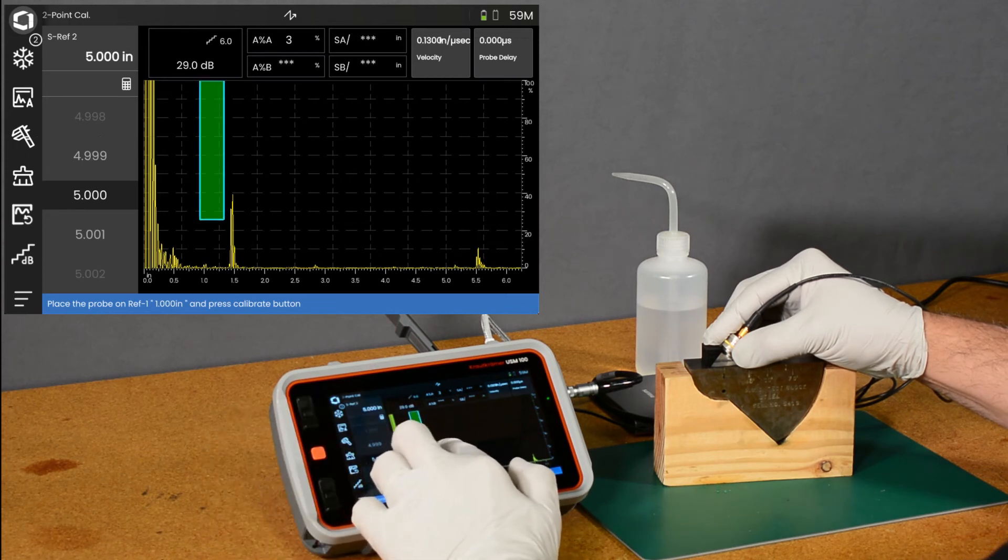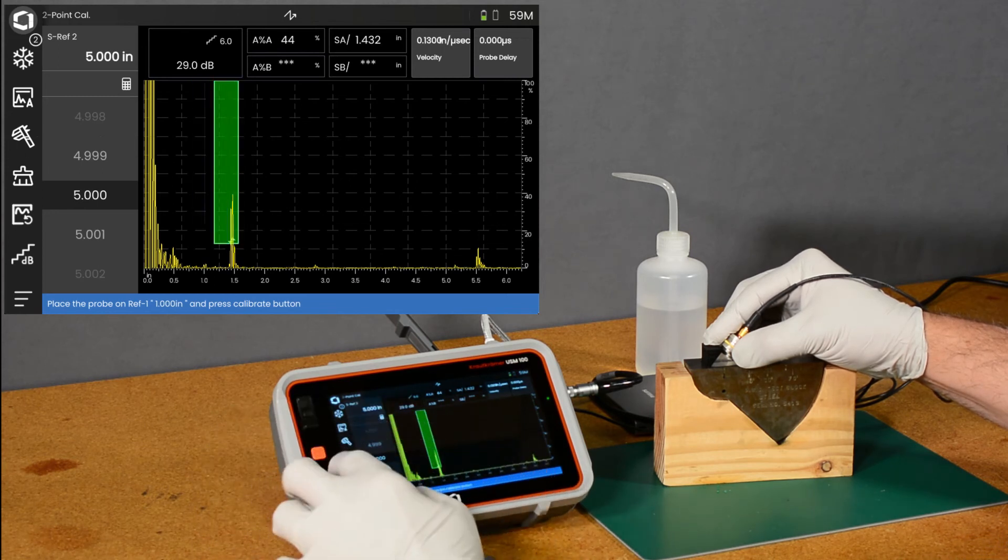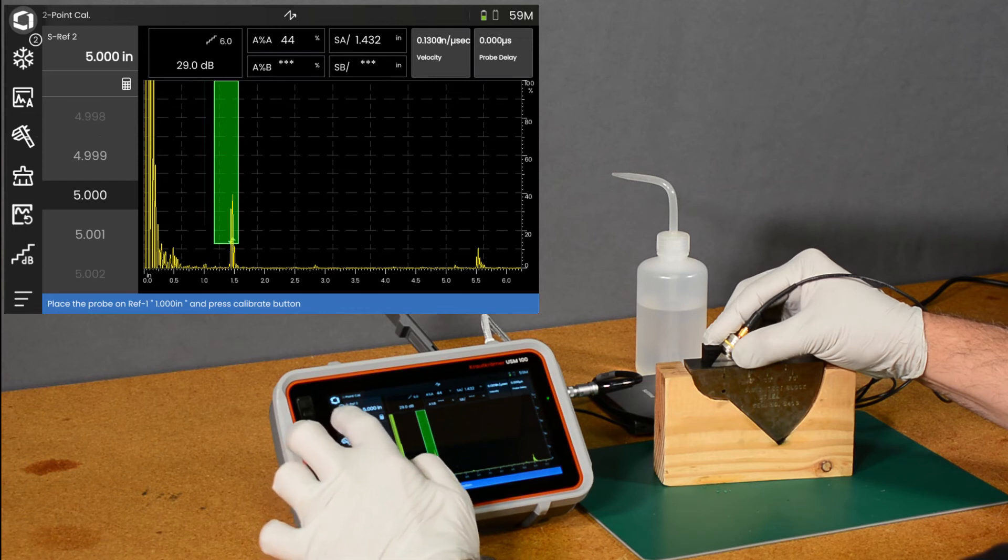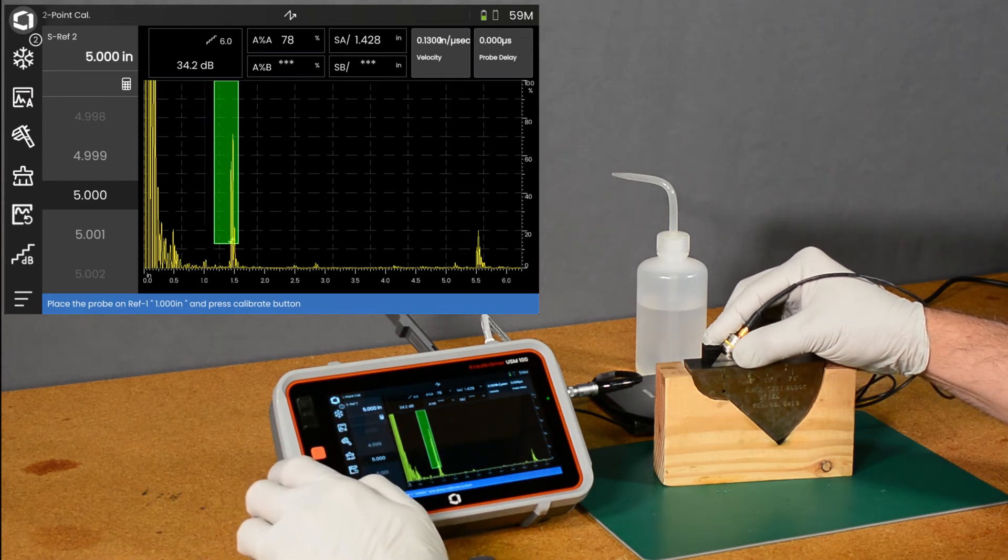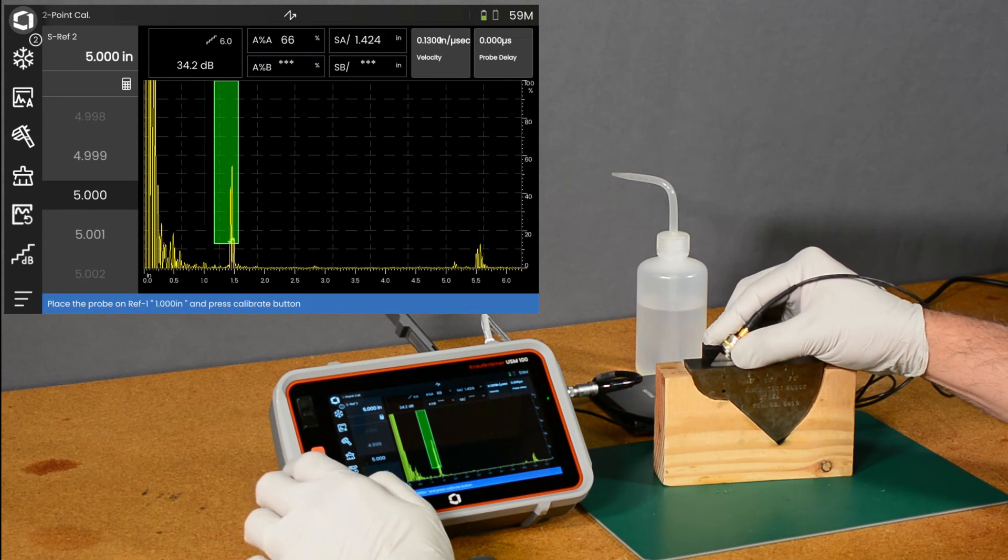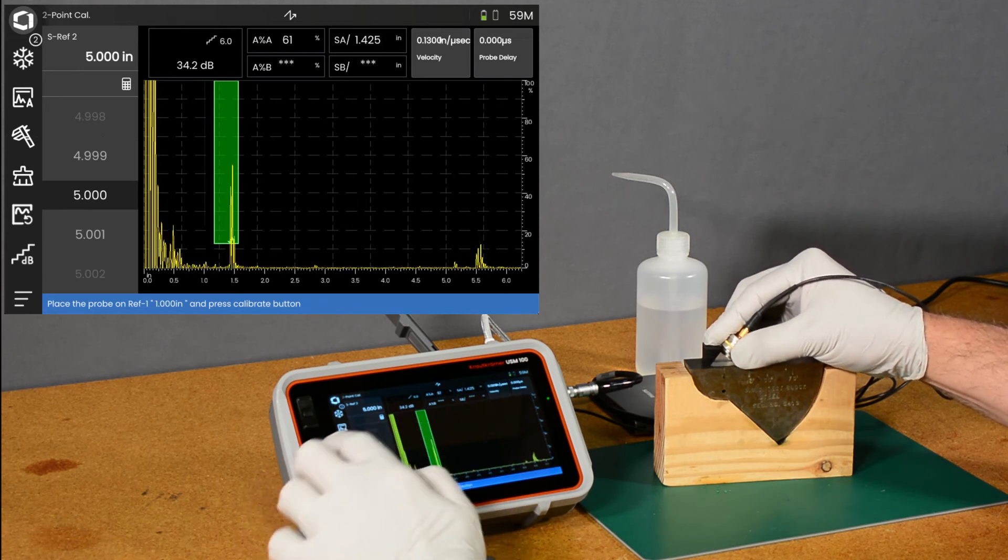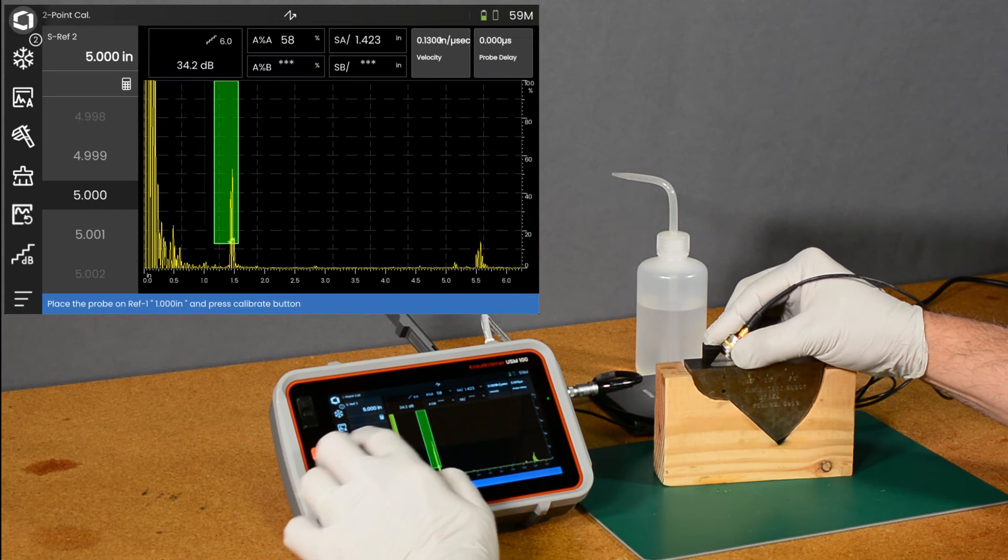we can drag our gate over the echo and let's get that up to 80% screen height. We'll use the auto 80 feature to bring that up. Get it peaked up there. Okay.